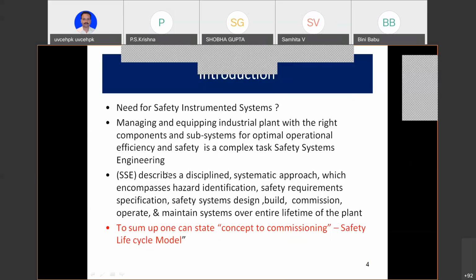Now, safety system engineering is a disciplined, systematic approach which encompasses hazard identification. We identified the hazard. The pump churning will blow up the place. The vapor cloud explosion will take place. And then we also said that on high pressure, the reactor may also fracture, and you may get a reverse flow, hence protected. So we had identified all the hazards in that little hypothetical plant.